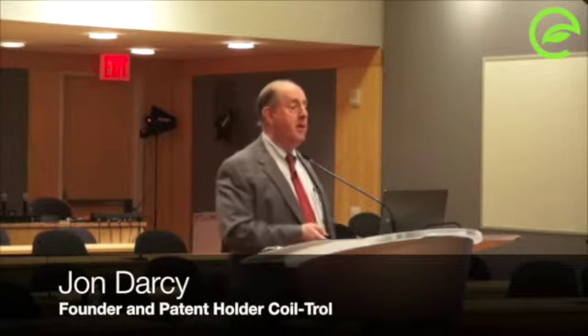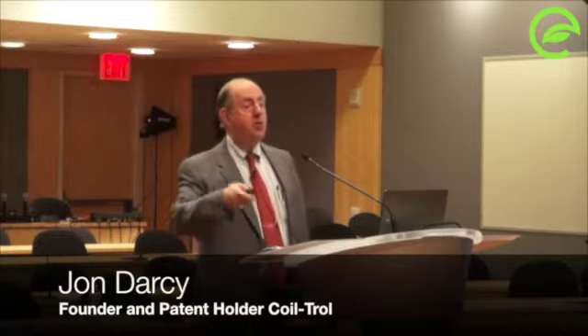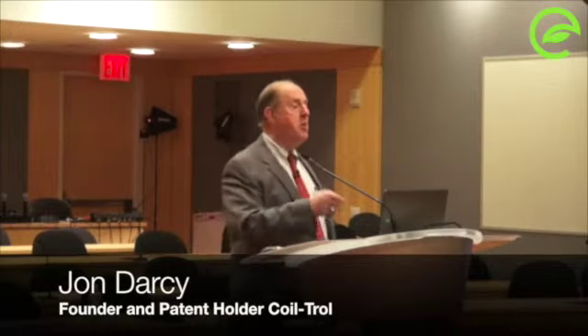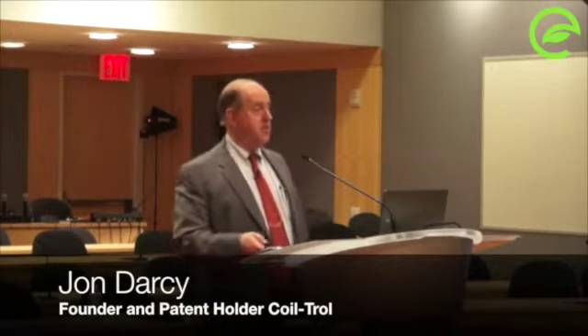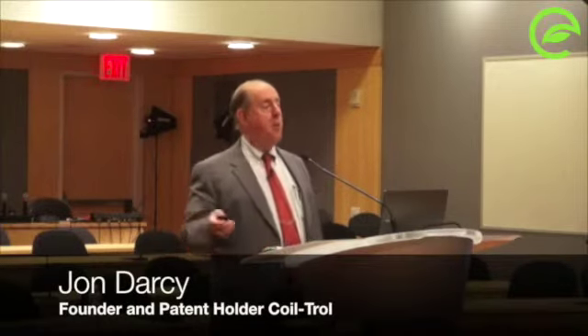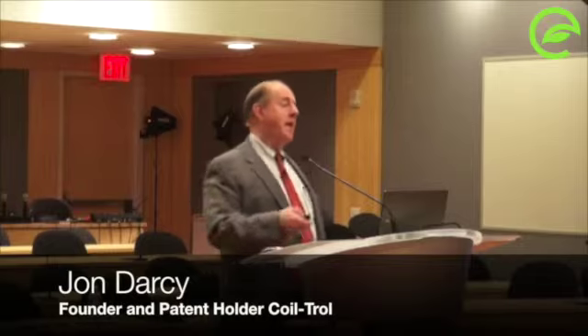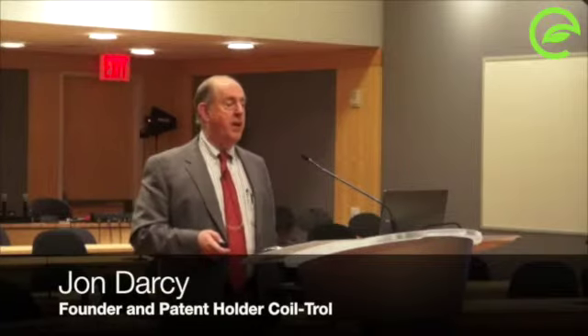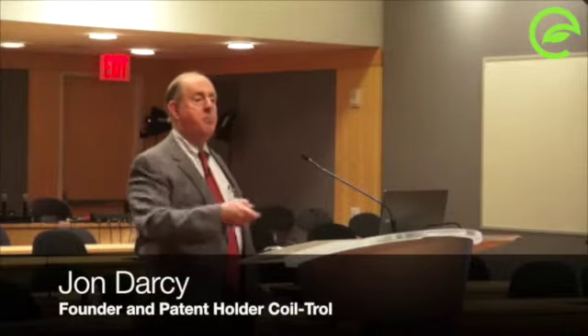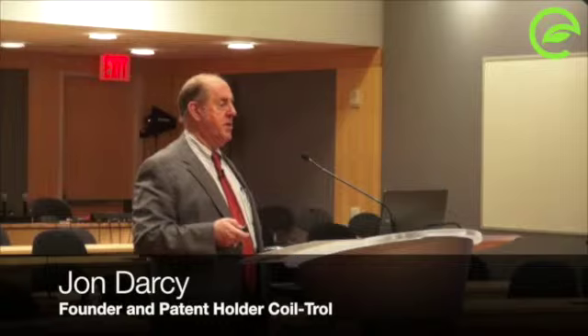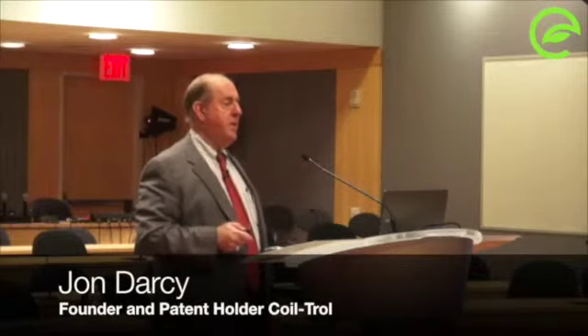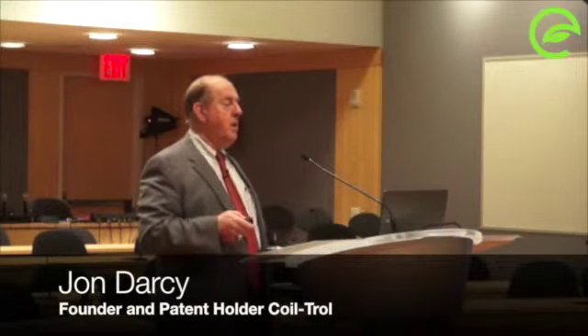But we're doing it on a per air handler basis and a per building zone basis, because the air handlers are done by zones. So I can treat the upper part of the house differently than I can the lower part of the house, which means that on a lot of those days where I don't have the sun load and I don't have the humidity load, I can operate at 64 degrees discharge temperature on the air handler, and everybody's happy. Okay?